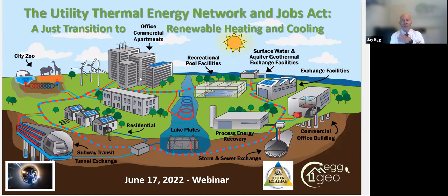One of the most important things to realize when you consider a thermal energy network in a city—and this is true whether you're in Albany, Toronto, or St. Paul, Minnesota—is that your commercial office buildings are typically going to be cooling dominant. In lay terms, that means those buildings have extra energy even during the -20°F days of winter, because they're so filled with equipment, people, and computers. If you ever want to confirm this in your own mind, just take a look at a city skyline during the middle of winter when it's snowing, and you will see steam plumes rising from the top of the buildings.